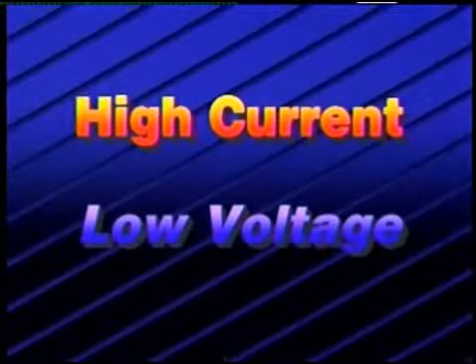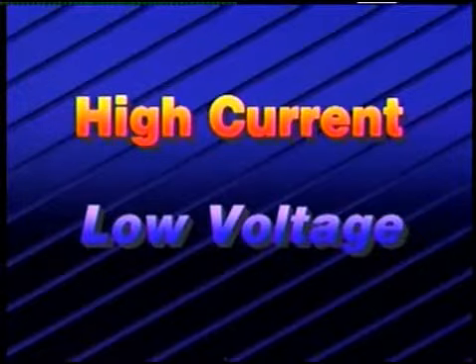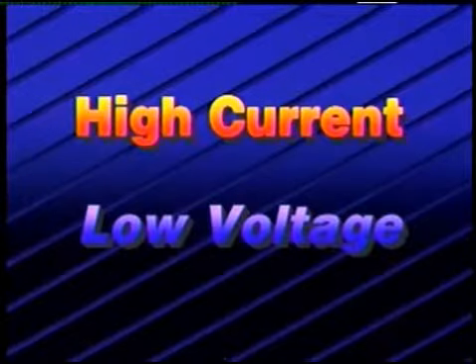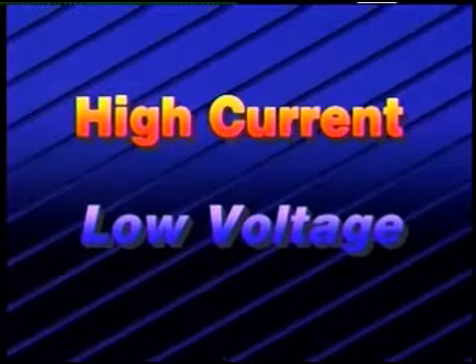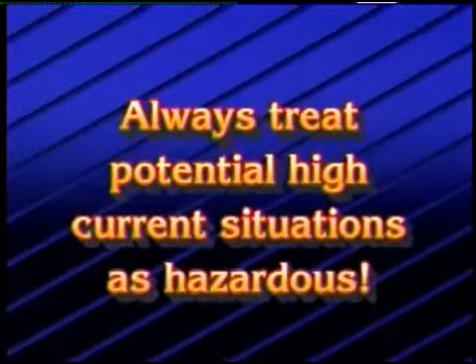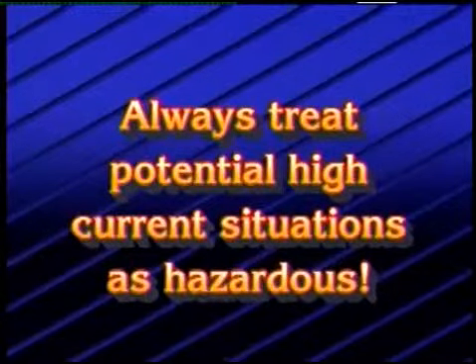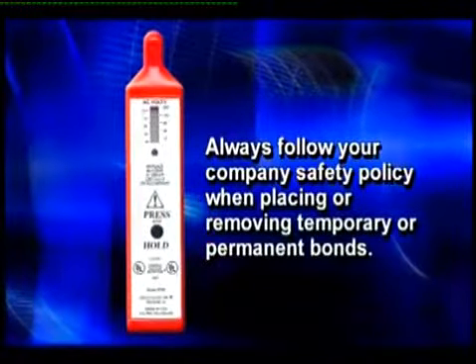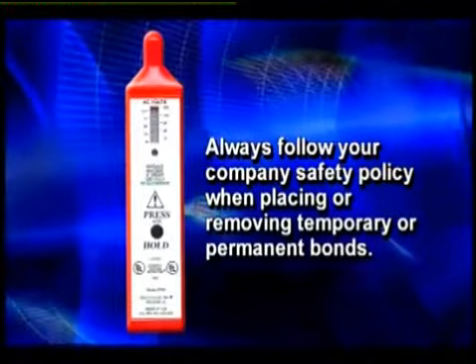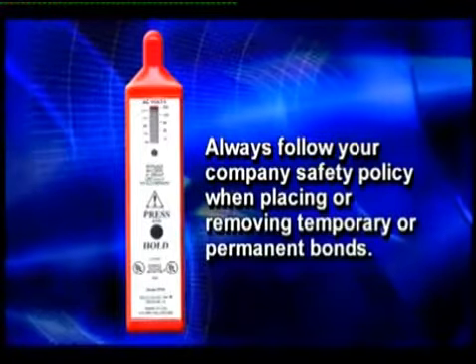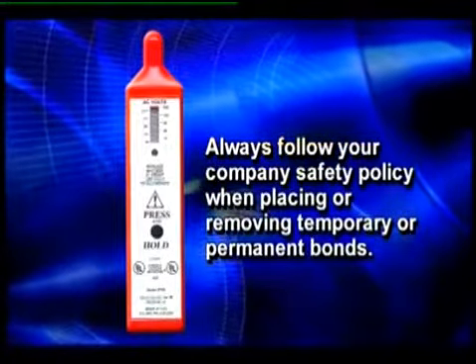A condition can exist whereby large currents can flow while voltages are quite low. As long as this condition persists, it is not hazardous. If, however, this circuit is opened so that the current flow stops, the voltage on one side of the open can immediately reach dangerous levels. Always treat potential high current situations as hazardous. Always look for indications of high current, such as discoloration, excessive heating, smoke, etc. Test current-carrying conductors with the F.V.D. before making any contact with them. Always follow your company's safety policy when placing or removing temporary or permanent bonds.